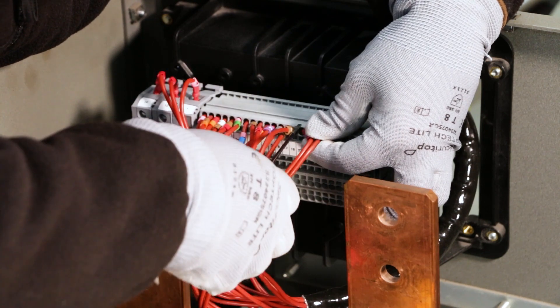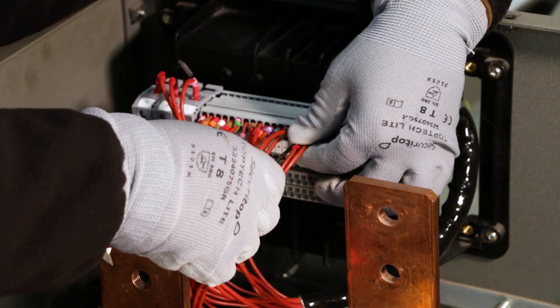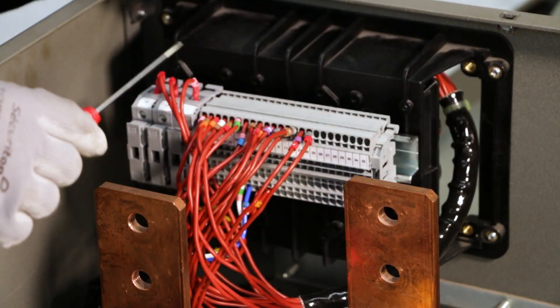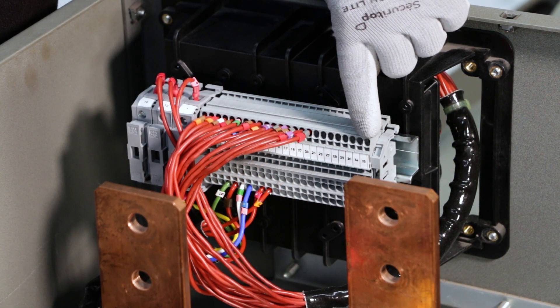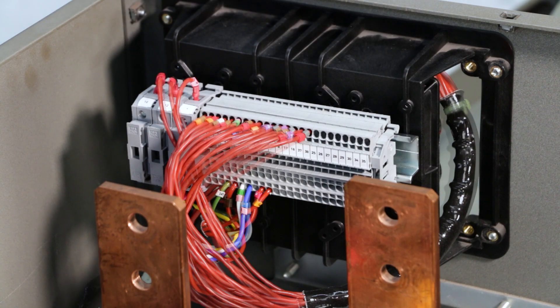Terminals 7-8, 17-18, and 37-38 should be used if your alternator is equipped with one or three current transformers. The inputs and outputs can be connected to the last available terminals on the terminal block.